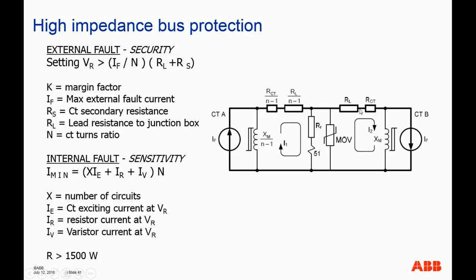If you have a huge resistance here, obviously you will get a high voltage if you have a current flow, because the short circuit current is a product of your system design, your power system. So you cannot change it. And this winding resistance of the CT, again, you cannot change it. That comes with the manufacturer. When you buy and specify this CT, you are stuck with it. So you cannot change it.